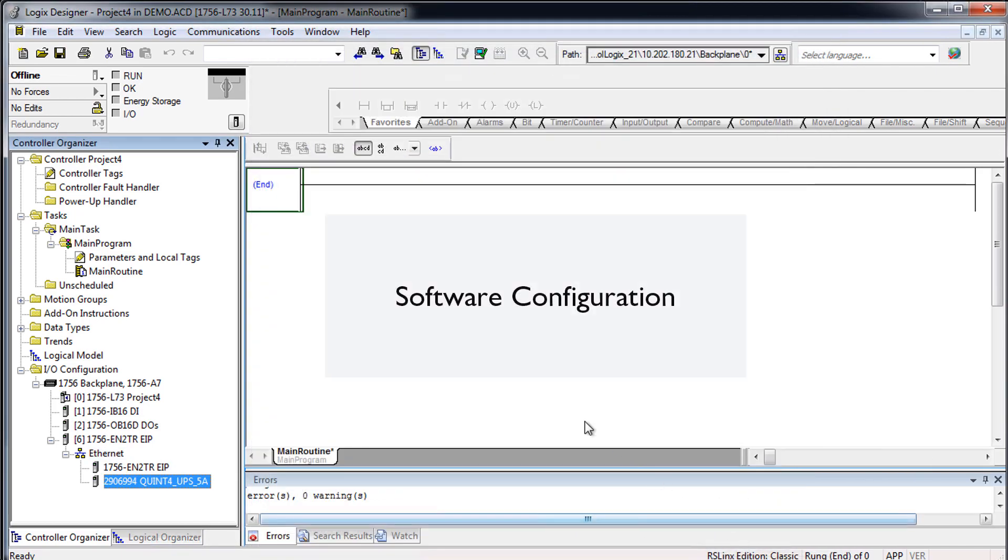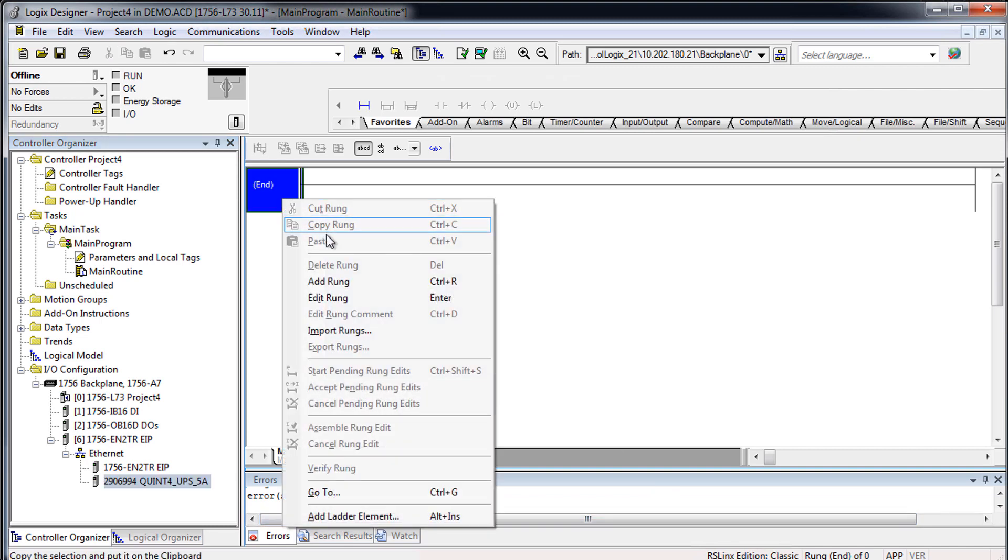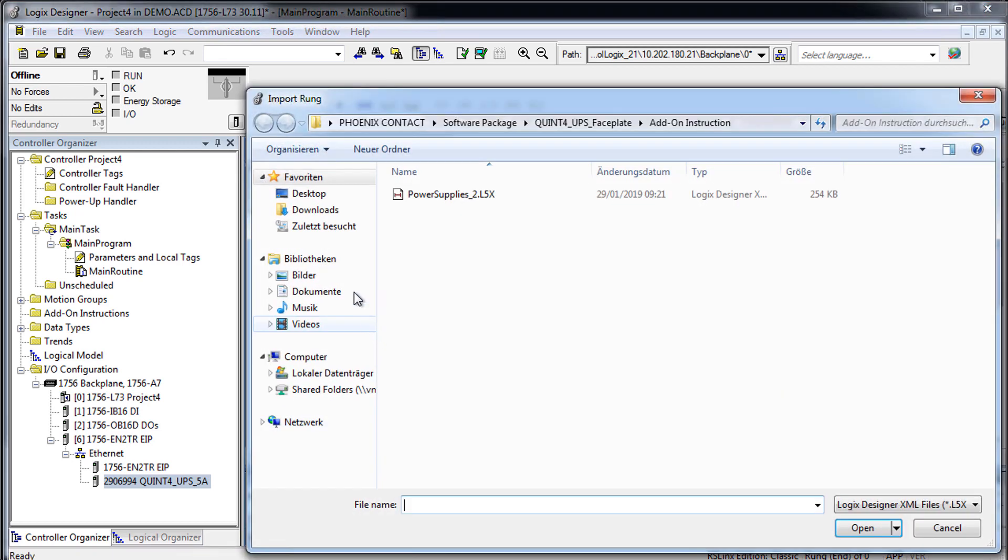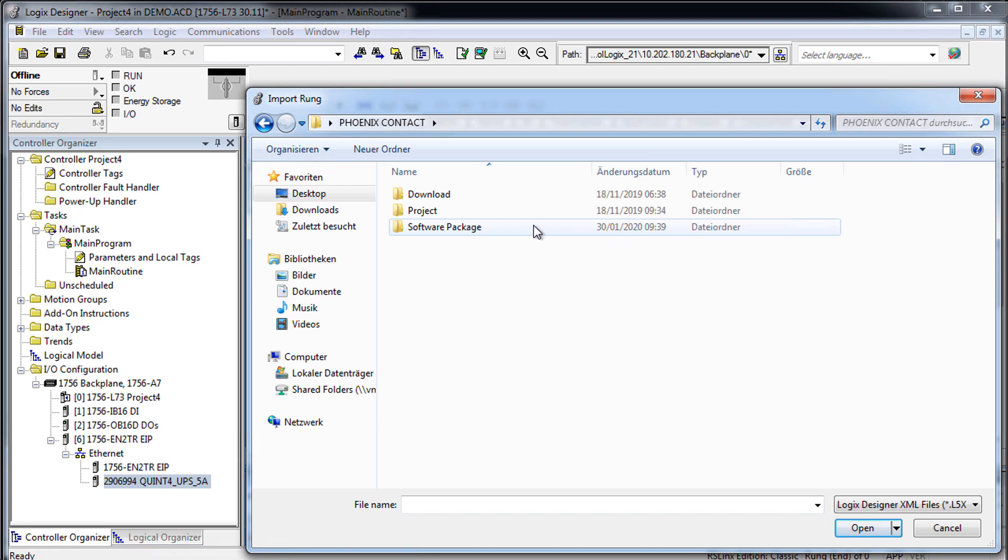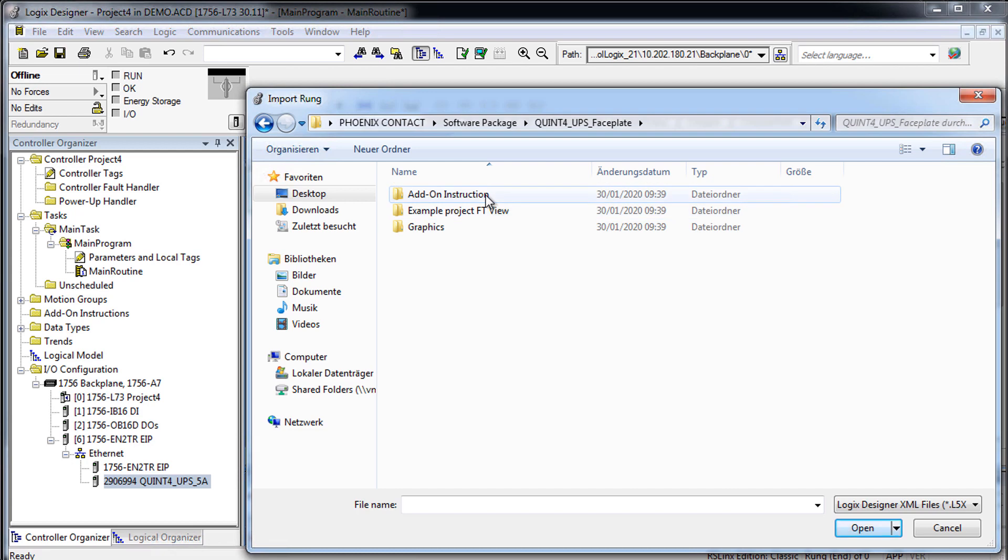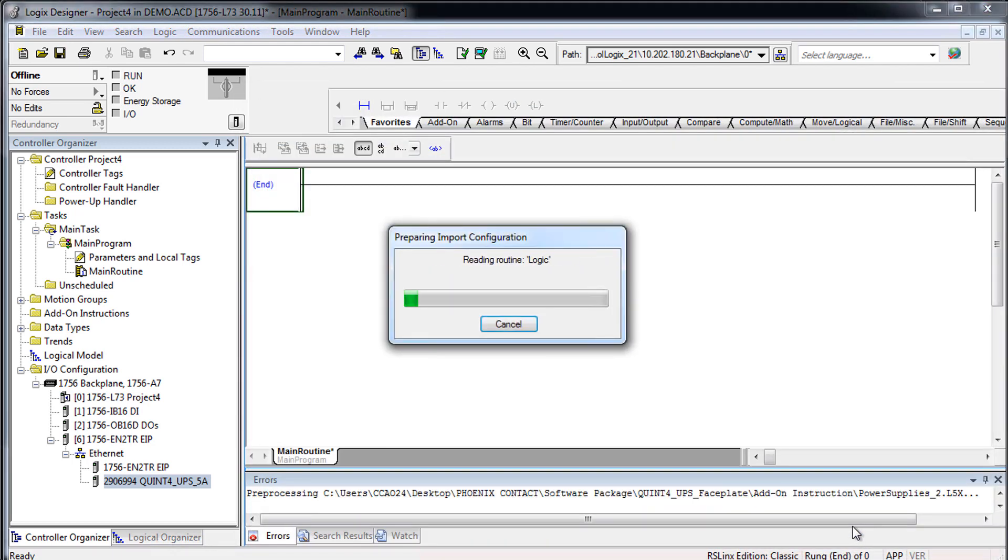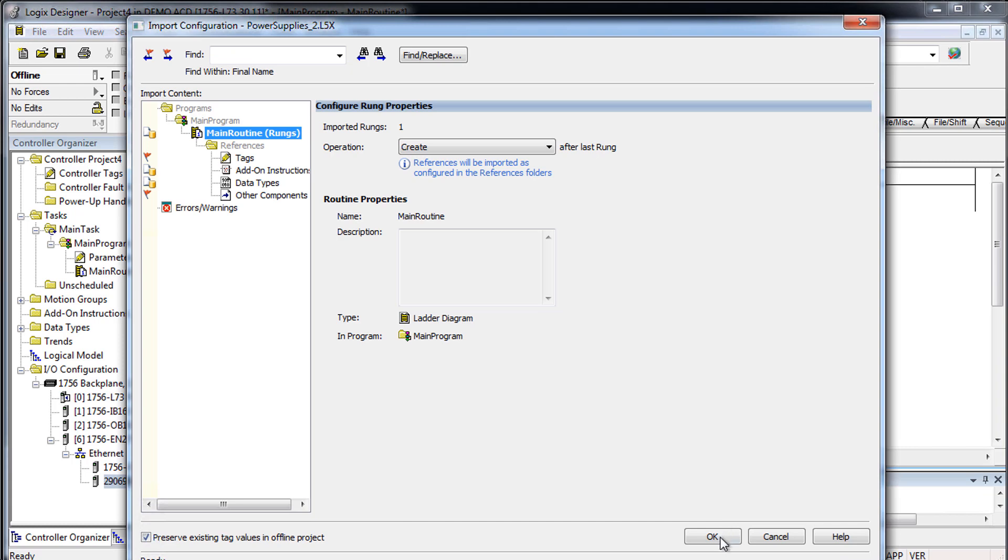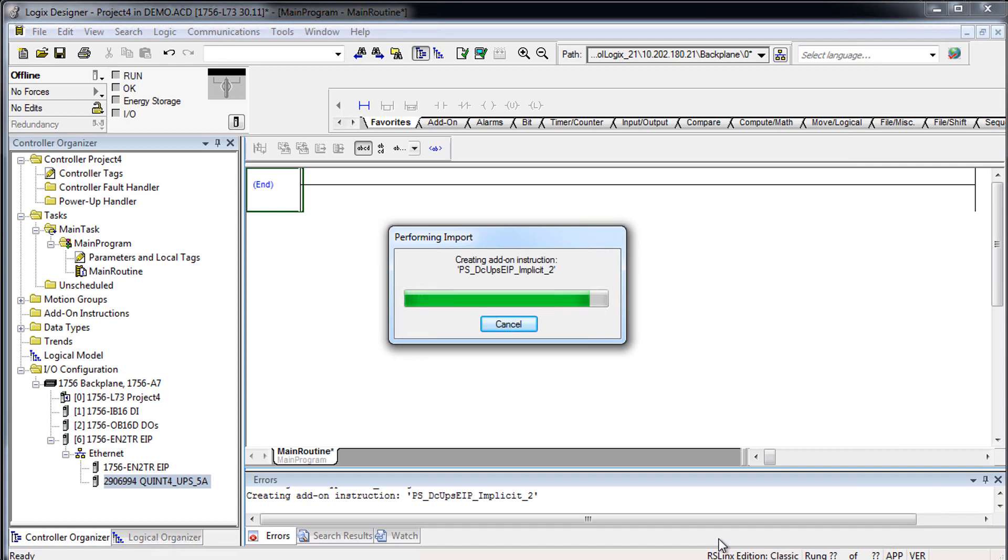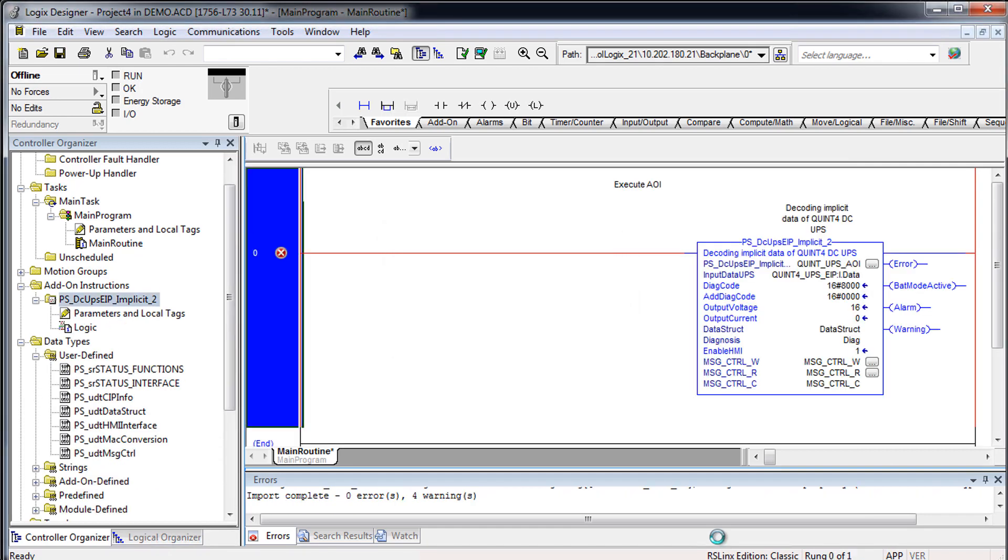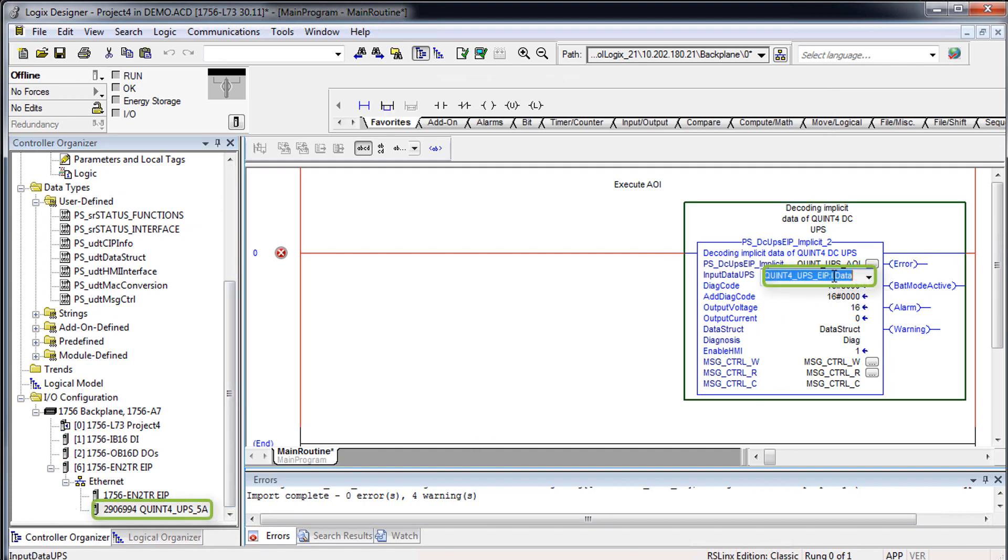Software configuration. For the software configuration, please open the main program and import the power supplies rung from the Phoenix Contact software package. Change the name of the process data connection at the AOI to the name of your previously configured UPS.